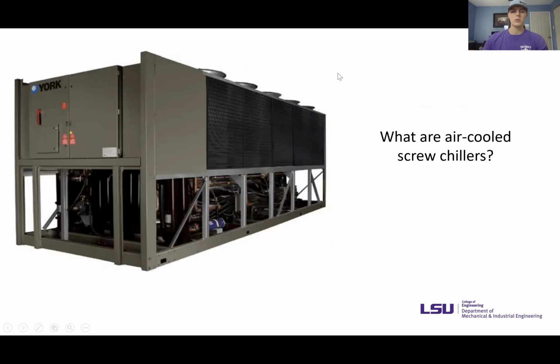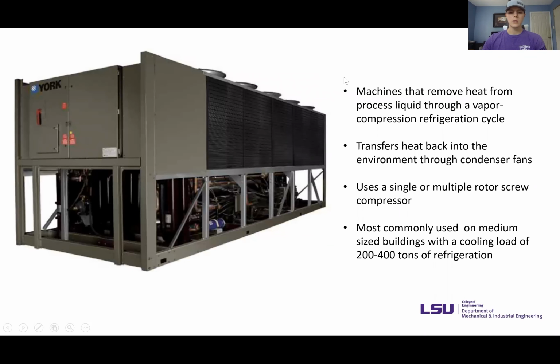So what are air-cooled screw chillers? They're machines that generate chilled water to provide air conditioning to a building. They remove heat from processed liquid through a vapor compression refrigeration cycle. So what that means is the refrigerant is used to move unwanted heat between the evaporator and condenser, where the fans pull air across the condenser and disperse the unwanted heat back into the environment.